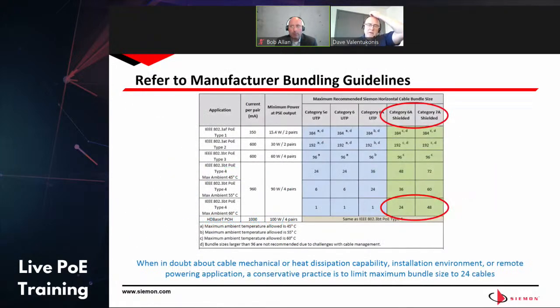This here is a manufacturer guideline—this happens to be Siemon, though a lot of manufacturers may have it. It talks about the bundle size, the maximum bundle size for different media types, as you go from the top of the screen, which is type 1 PoE, all the way down to type 4 PoE operating at that 60 degree limit we talked about—actually getting up to 75 degrees C overall with the heat rise.